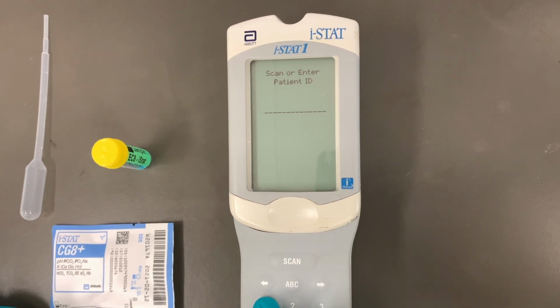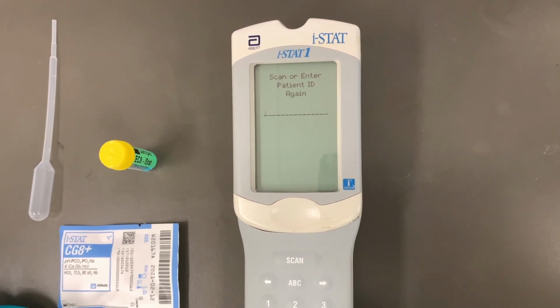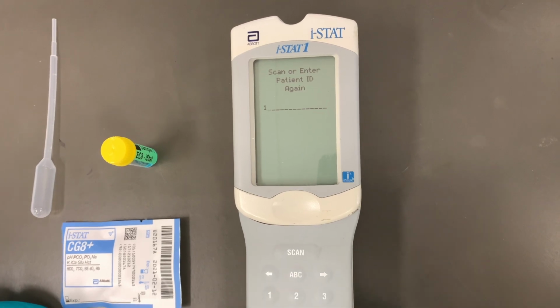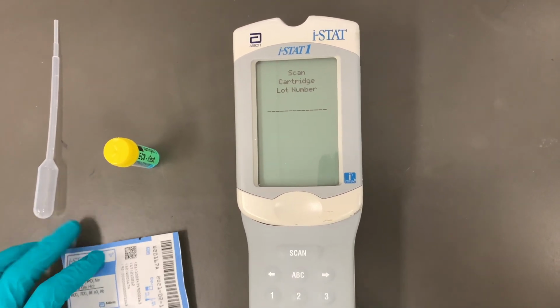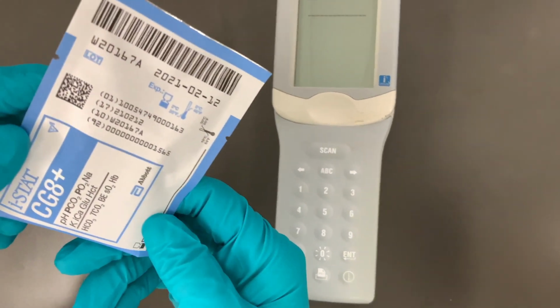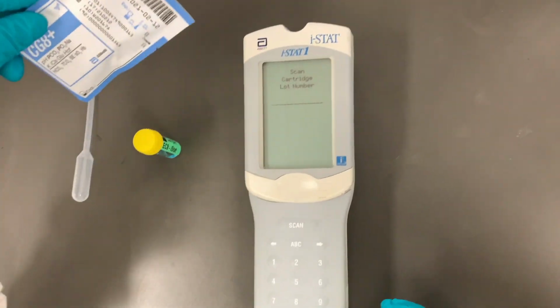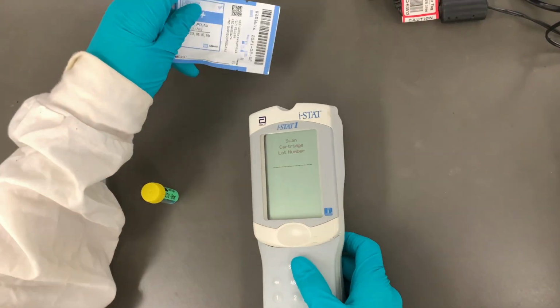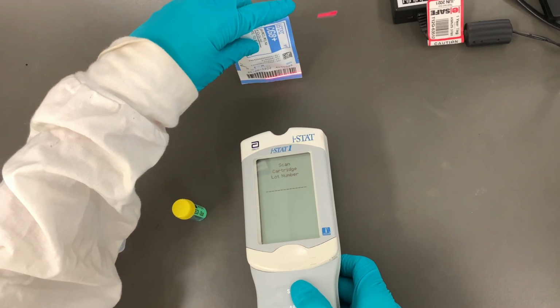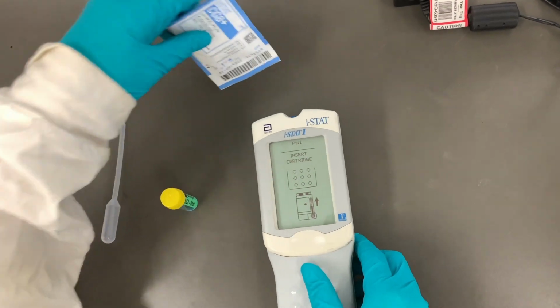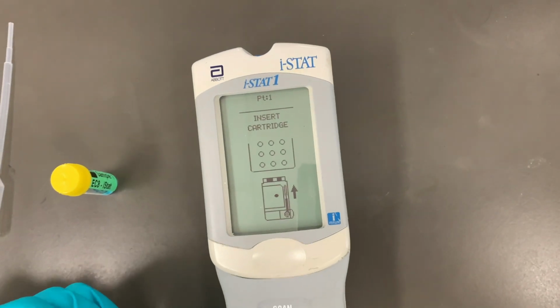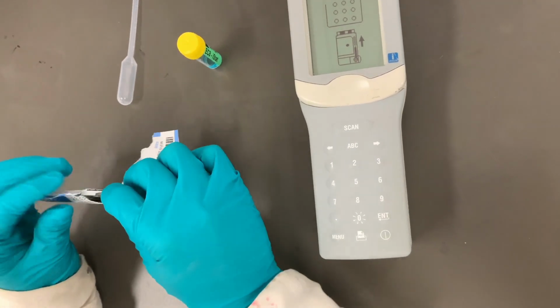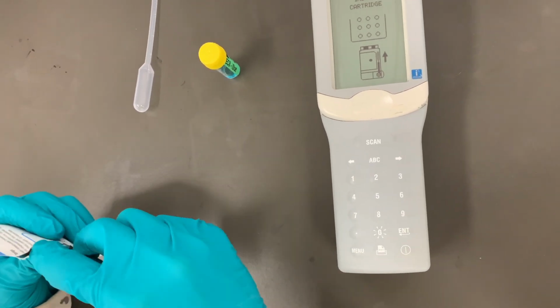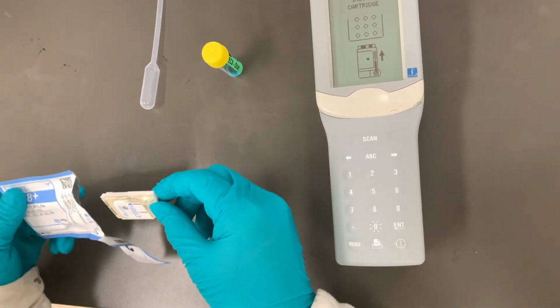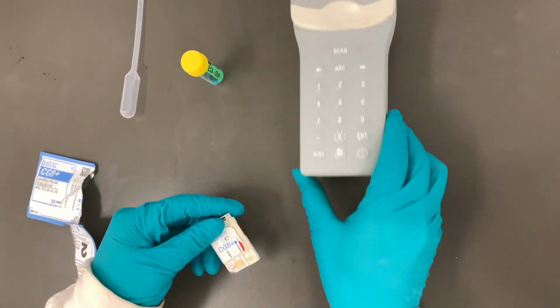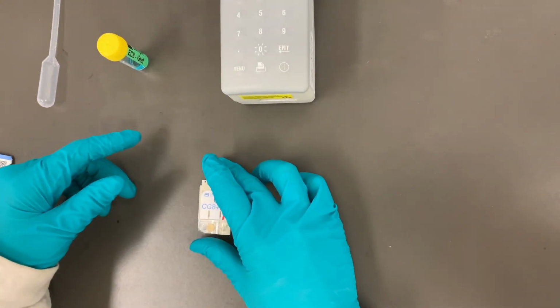In this case we are using 1 as our patient ID number, but always double check if the patient details are correct. After this, always check if you have the correct cartridge type and is still within the expiry date. You can now scan your cartridge lot number and it will display Insert Cartridge. Before this, open the cartridge pack, and this may be the hardest part of the test. Normally, you use a syringe or catheter, but in this case, we'll be using a transfer pipette.